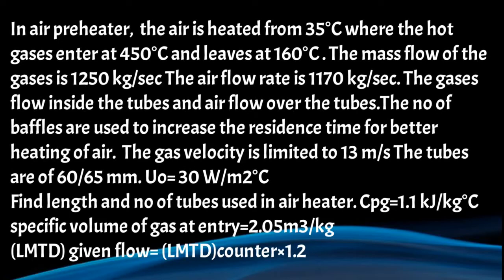The gases flow inside the tubes and air flows over the tubes. Baffles are used to increase the residence time for better heating of the air. The gas velocity is limited to 13 meter per second. The tubes are 60 or 65 millimeter. Taking overall heat transfer coefficient as 30 Watt per meter square degree Celsius, find the length and number of tubes used in the air heater. Take CPG equal to 1.1 kilojoule per kilogram degree Celsius and specific volume of gas at entry VGI equal to 2.05 meter cube per kilogram. LMTD of given flow equals LMTD counter multiplied by 1.2.